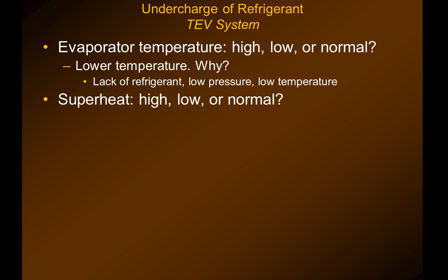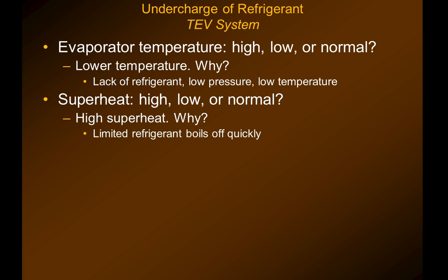Superheat — is it going to be high, low, or normal? We know that TXVs maintain superheat over a wide range of conditions. However, in a refrigeration system there's not a lot of refrigerant, so many times the TXV is not going to keep the superheat at a normal level. Very little refrigerant leaking out of the system is going to cause the TXV not to be able to regulate that. So you're going to have higher superheat because there's a limited amount of refrigerant in the system.